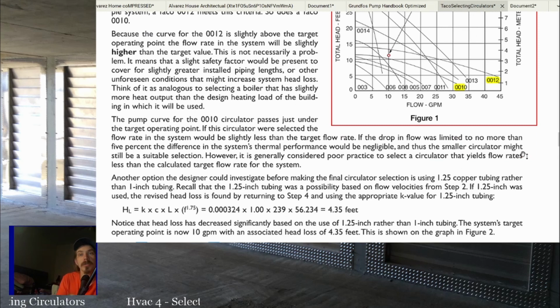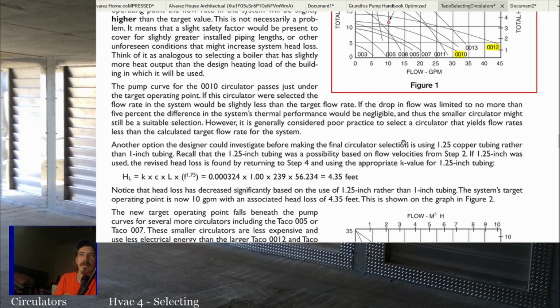So another option you could do is investigate before you pick the circulator. If you're designing a system from scratch, you can say, all right, well, what if I use 1.25 inch instead of 1-inch pipe, right? And it basically changes all your calculations starting at step 3. So if you're like, I don't want a 0012 or 0010, those are high head loss pumps, if I go with 1.25 inch instead of 1-inch, and we redo all those calculations.